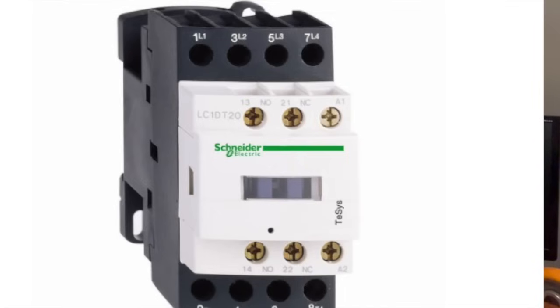So what I ended up doing was I actually had to go downstairs to the control system, and I had to take the air compressor off button, and what I did is I ran it through a latching relay to where the ride still functioned the way it was supposed to. I didn't interrupt the ride logic at all. But what I did is I made sure that when the air compressor off button was pushed, it latched a relay in. And that was the only relay. It had nothing else to do with the ride or anything else. It was simply just a tattletale button.